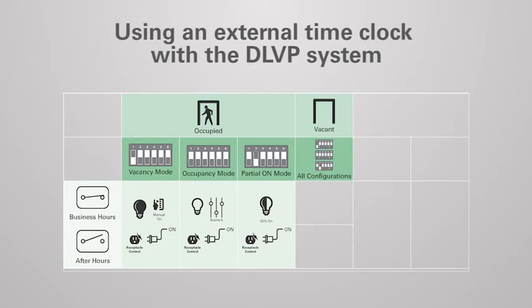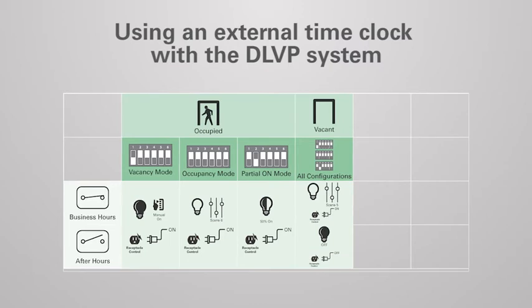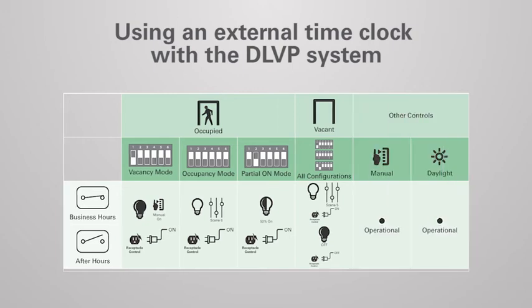When the space is unoccupied, all configurations operate in the same manner based on the time clock mode. During business hours, if a space becomes unoccupied, lighting will go to user programmable scene number five and receptacles will remain on. After hours, if a space becomes unoccupied, the lighting will turn off and receptacles will follow after a 30-second delay. Manual wall station and automatic daylight controls will be operational to adjust light levels as needed any time of the day.